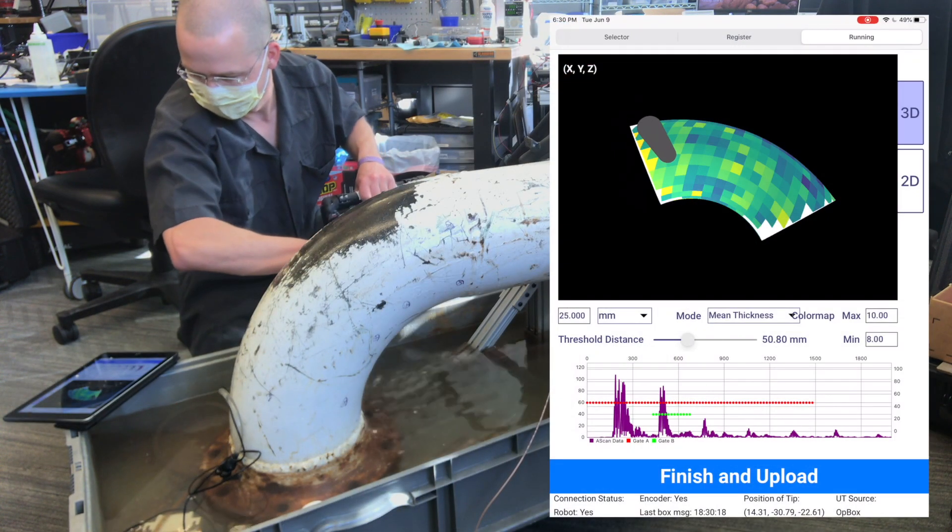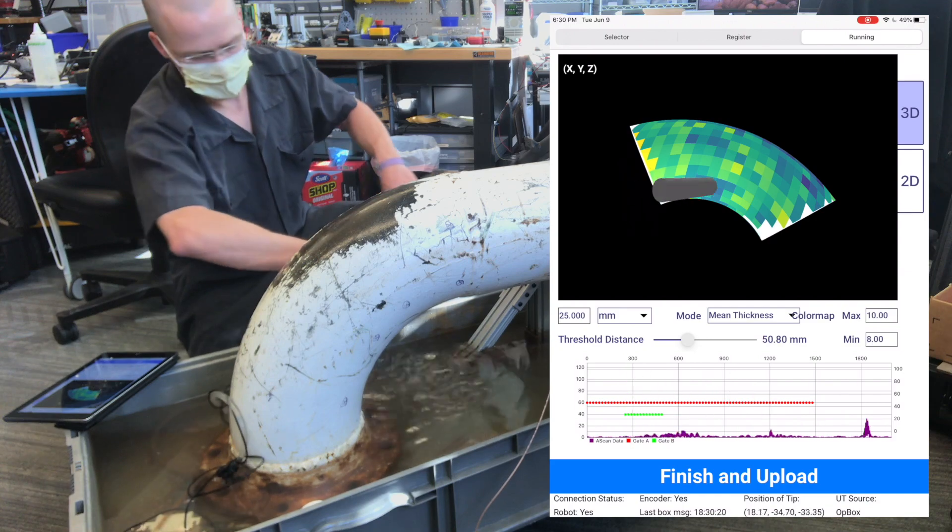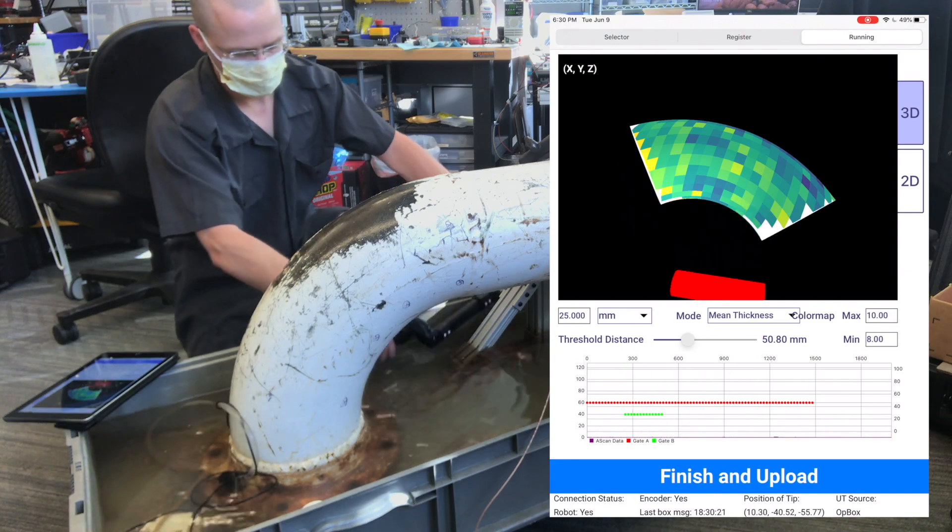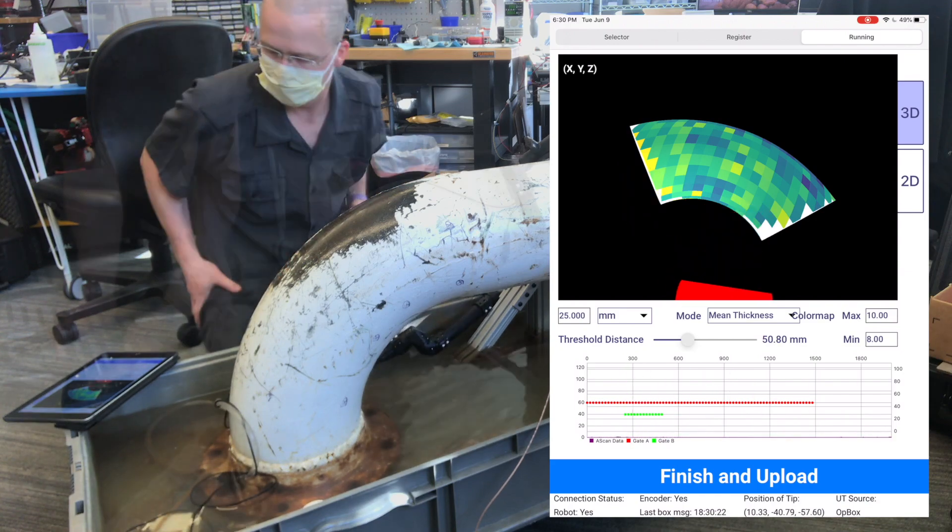In this case, I was able to complete a 1-inch gridded scan of an entire 8-inch elbow in just under 10 minutes.